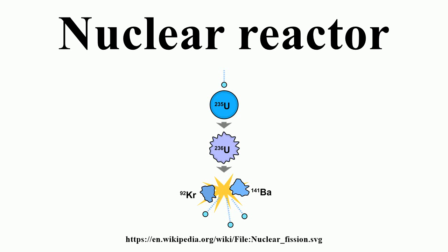Nuclear reactors generally have automatic and manual systems to scram the reactor in an emergency shutdown. These systems insert large amounts of poison into the reactor to shut the fission reaction down if unsafe conditions are detected or anticipated. Most types of reactors are sensitive to a process variously known as xenon poisoning, or the iodine pit. The common fission product Xenon-135 produced in the fission process acts as a neutron poison that absorbs neutrons and therefore tends to shut the reactor down.